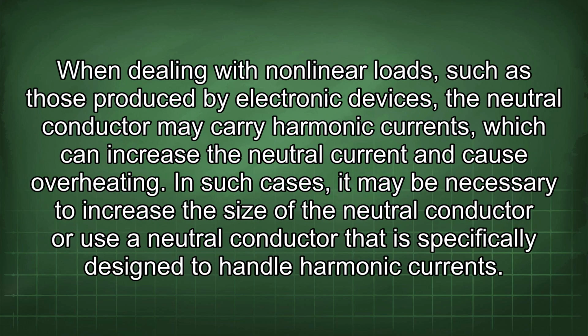When dealing with nonlinear loads, such as those produced by electronic devices, the neutral conductor may carry harmonic currents, which can increase the neutral current and cause overheating. In such cases, it may be necessary to increase the size of the neutral conductor or use a neutral conductor that is specifically designed to handle harmonic currents.